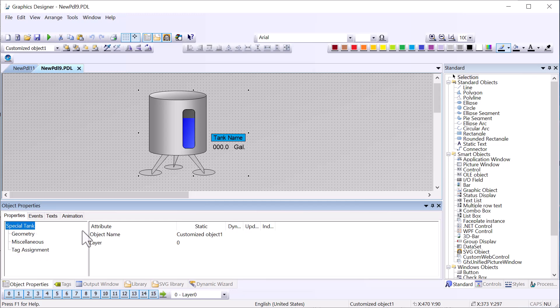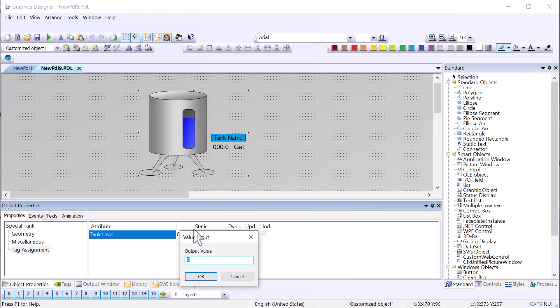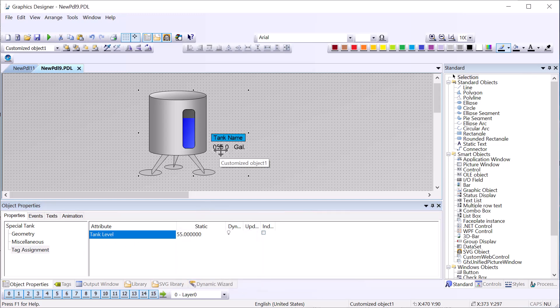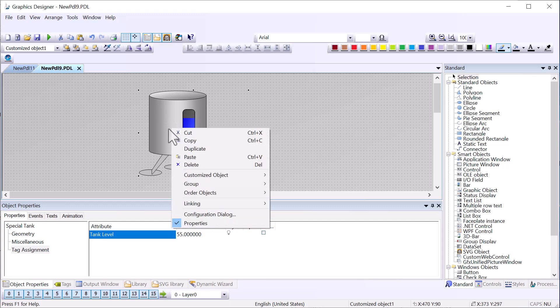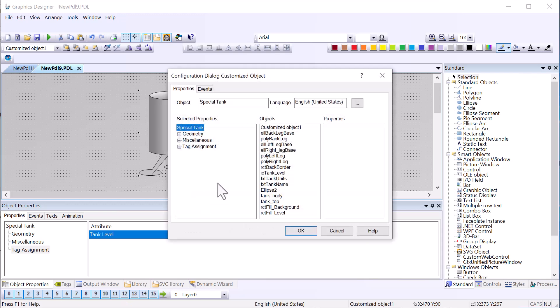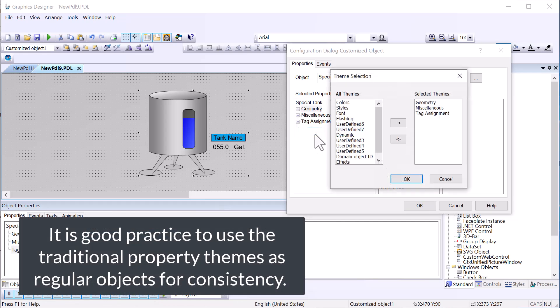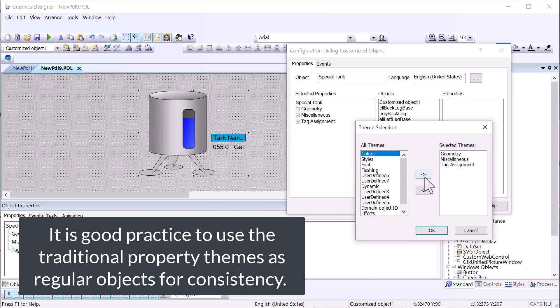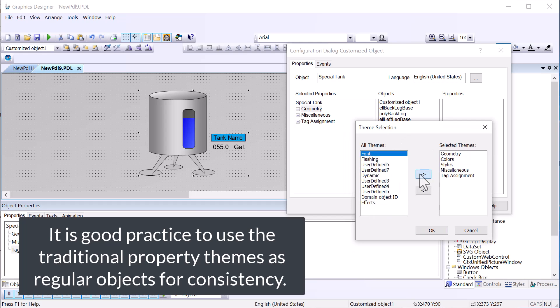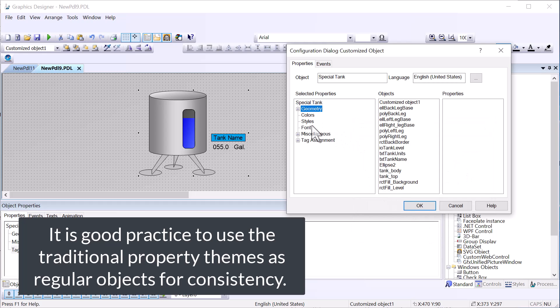Now the property topic is changed to Tag Assignment. There's Special Tank — that's the type of object this is — and I have a property for my Tank Level. If I put a number in it then it's going to change the output value of the IO field, and that's exactly what customized objects were made to do. If you know that fact you're 95% of the way there. I'll right-click and do Configuration Dialog again, and it's also good practice to open Theme Selection and put in all the standard themes and place those relevant properties there.